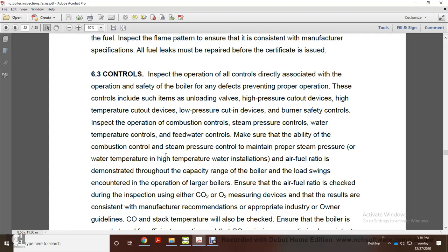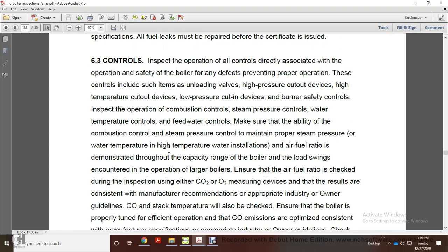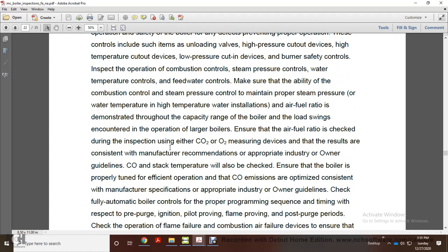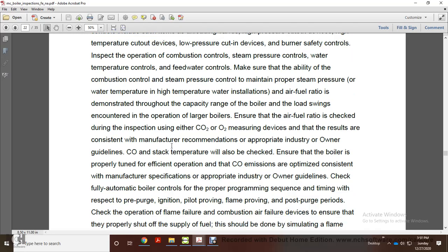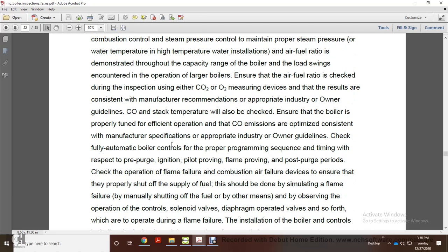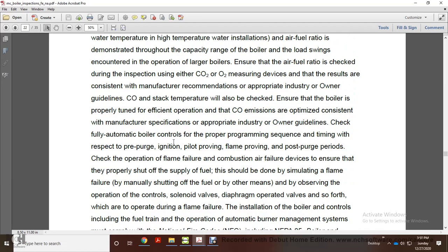Consider load swings encountered in the operation of large boilers. Ensure the air-fuel ratio is checked during the inspection with a CO2 (carbon dioxide) or oxygen measuring device, consistent with manufacturer recommendations and appropriate industry or owner guidelines. CO2 and carbon monoxide stack temperature will also be checked to ensure the boiler is properly tuned for efficient operation, with carbon monoxide emissions optimized, consistent with manufacturer specification and appropriate industry or owner guidelines.